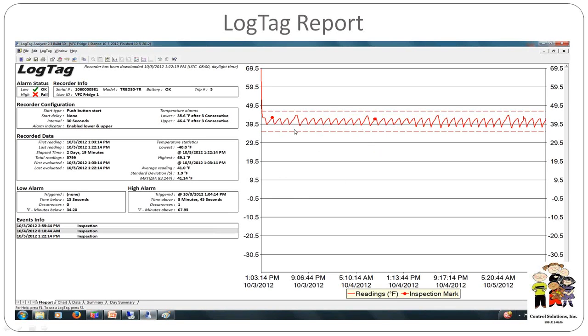You'll notice some of my data is a little higher, and it's almost repeatable - those are defrost cycles. With the alarm delay, if a value went too high and stayed there long enough, it would trigger the alarm. But if I just opened the door and the temperature went just above and back down, it won't go into alarm.